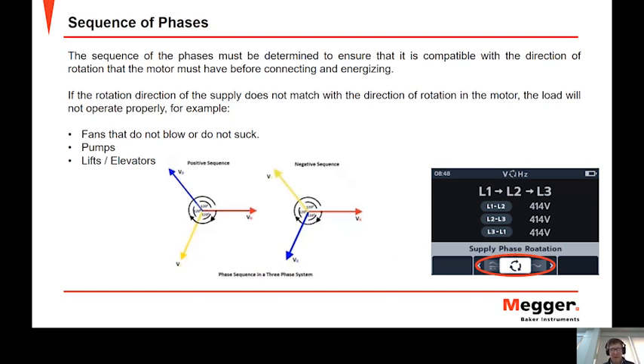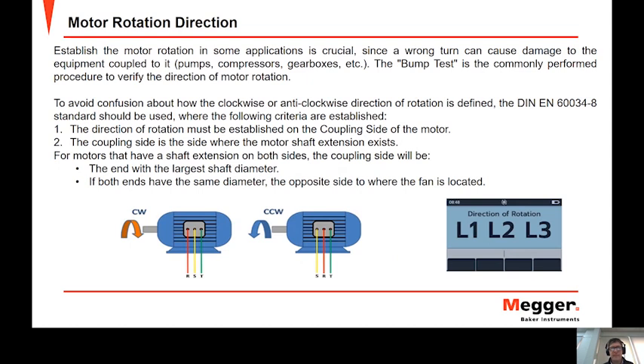So the MTR will display that measured voltage between the phases, and then also that sequence L1 to 2 to 3, confirming that rotation. And then we compare that to the motor rotation direction. And if we have the same L1, 2, 3, then we know that the motor will rotate in the correct direction.